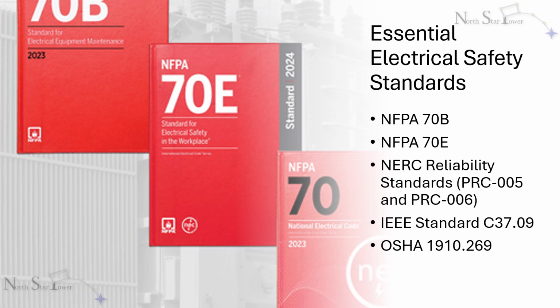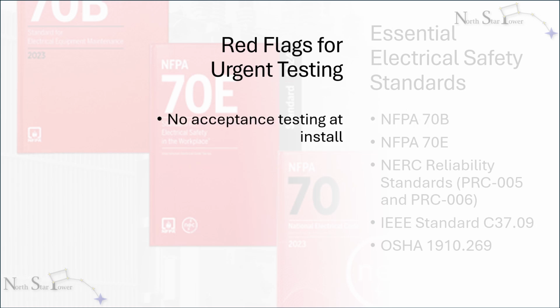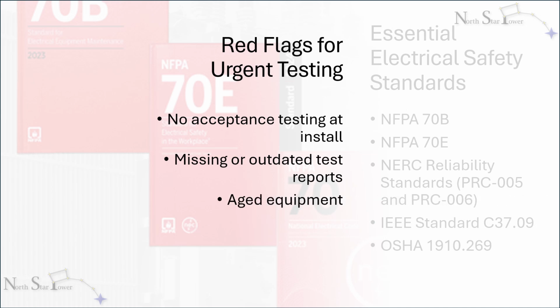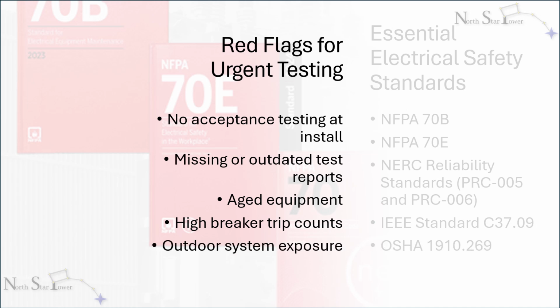Even with these standards in place, facility managers must stay alert to warning signs that signal a more urgent need for inspection. Red flags include missing acceptance testing at installation, outdated or absent test reports, antiquated or outdated equipment, high trip counts, outdoor exposure, recent fault events, and unexplained performance anomalies, all of which suggest increased risk of degradation or failure. In all cases, urgency increases when test data is missing, outdated, or inconsistent with manufacturer or industry benchmarks.